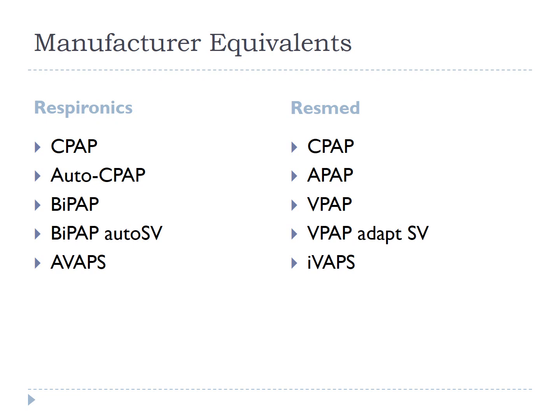And we can set up a rate, a backup rate. So if we're concerned that the patient maybe won't take as many breaths in a minute as they need, we can set a rate of 12, and it will ensure that the patient's respiratory rate is 12 breaths per minute. Respironics calls these devices a BiPAP. ResMed calls these devices a VPAP. V stands for variable, and bi obviously stands for bilevel.